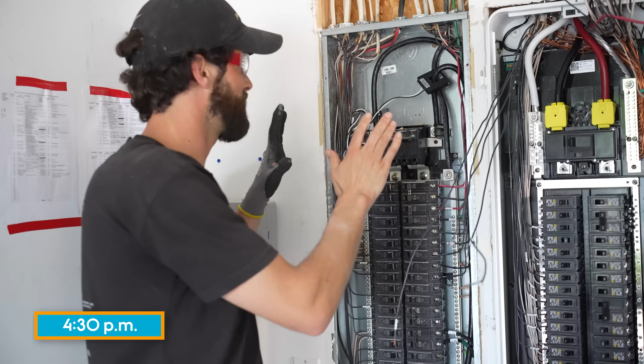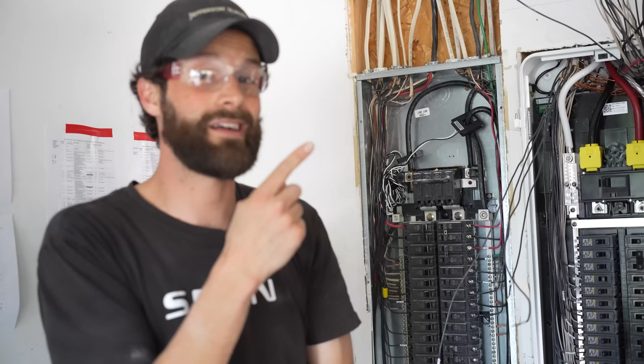We've got this panel landed. It's ready to be energized. We've been inspected. The utility's been out here. If you missed part 1, you got to check it out here. So the way to do it right is you turn all the breakers off so that when you flip the main, there's no load, there's no draw. Because let's just say, it's unlikely in a residence, but let's just say that all these draws, all these circuits were calling for load, were creating demand.